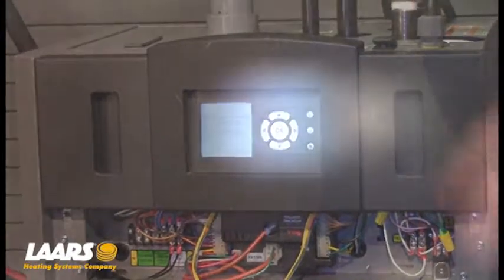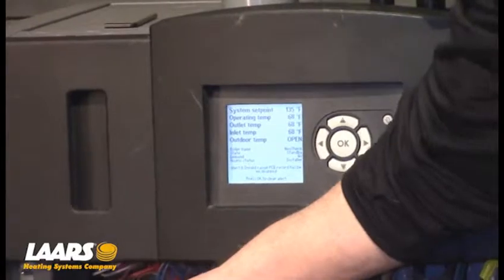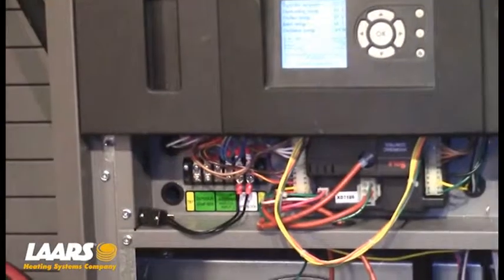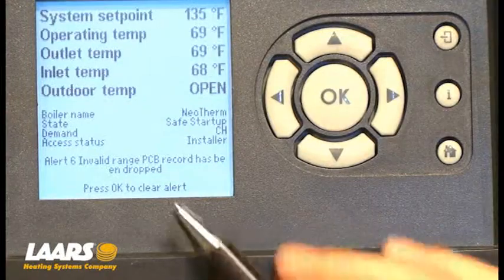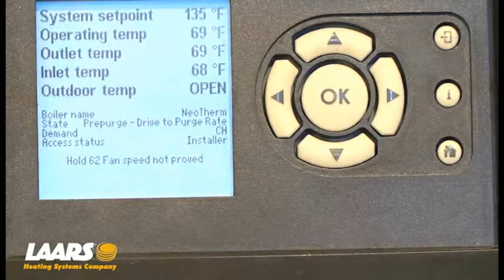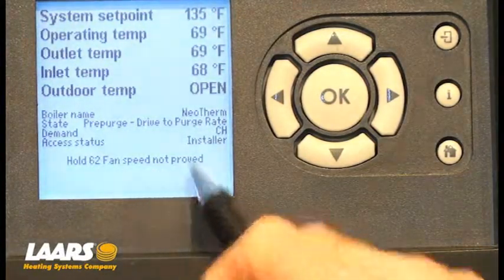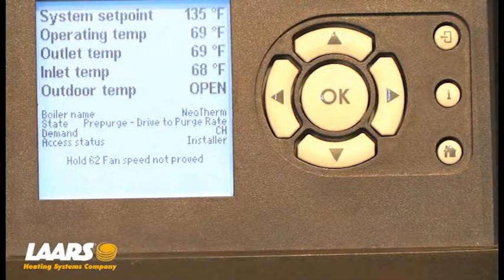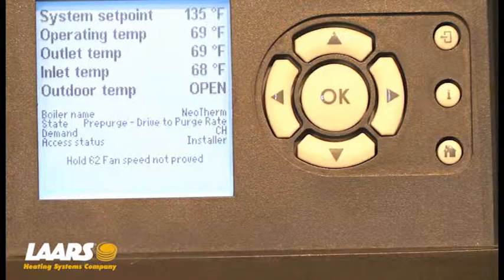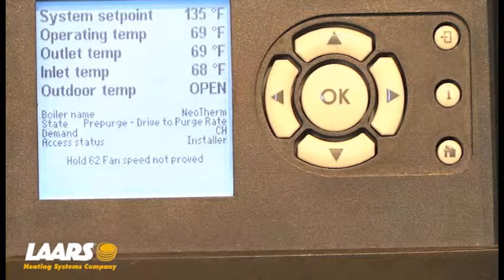Now that it's synchronized, we're on the home screen. We will give the boiler a call for heat — I wired in a small toggle switch. Here on the home screen, it will tell you the state is currently pre-purge, driving to purge rate. You will also see the hold 62, fan speed not proved. The reason the 62 hold is here is we're going into a pre-purge, which is clearing the chamber of any residual flue gases.